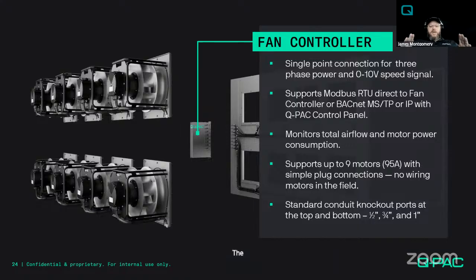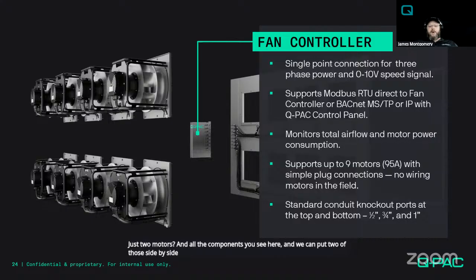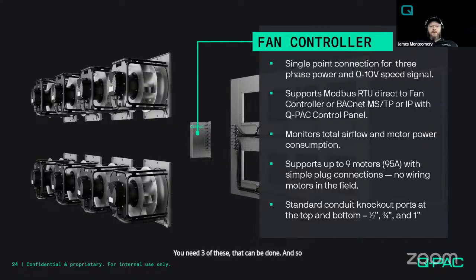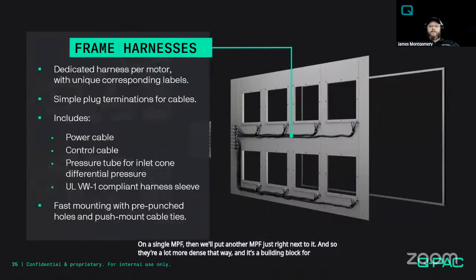The idea being if you need more than 9 fans to achieve your schedule or your CFM and static, then we can put multiple of these. And so this can scale down to just 2 motors and all the components you see here. And we can put 2 of those side by side and they can be connected with our adaptable frame bulkhead. You need 3 of these, that can be done. And so as your demand grows larger, the adaptability of this means that once we get up to 95 on a single MPF, then we'll put another MPF just right next to it. And so they're a lot more dense that way, and it's a building block for the Q-PAC system.